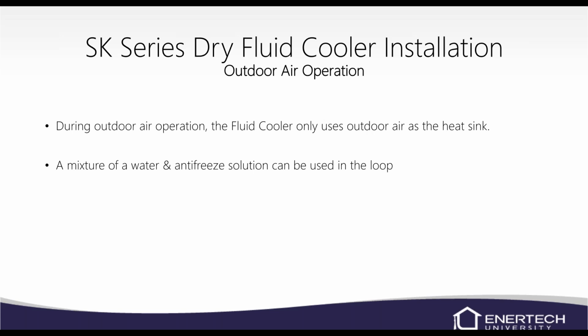During outdoor air operation, the fluid cooler only uses outdoor air as the heat sink. So it's very similar to an air source heat pump, except that we're using water instead of refrigerant in that coil. You can use a mixture of water and antifreeze in the loop, which I would recommend, especially if you think it's going to get near that 23-degree mark. Anytime it's going to get to 32, you're going to need some antifreeze in there. Normally, we already put antifreeze in our source loop, so it can run right through the fluid cooler with no issues with the antifreeze mixture. It'll be just fine.